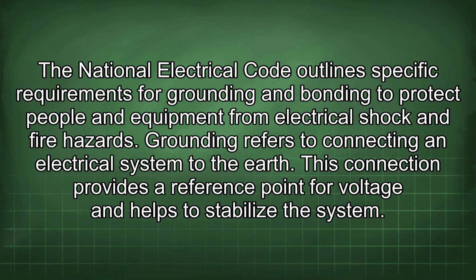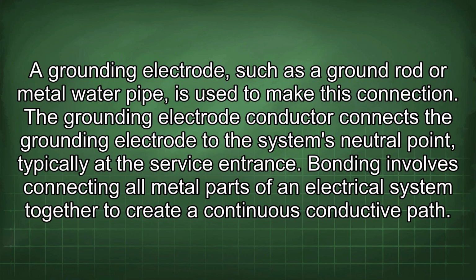Grounding refers to connecting an electrical system to the earth. This connection provides a reference point for voltage and helps to stabilize the system. A grounding electrode, such as a ground rod or metal water pipe, is used to make this connection. The grounding electrode conductor connects the grounding electrode to the system's neutral point, typically at the service entrance.